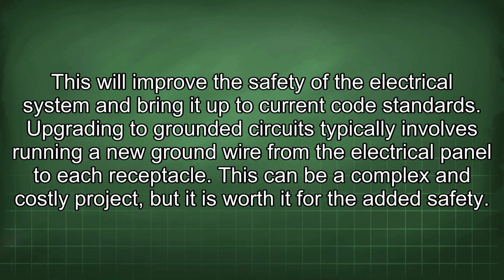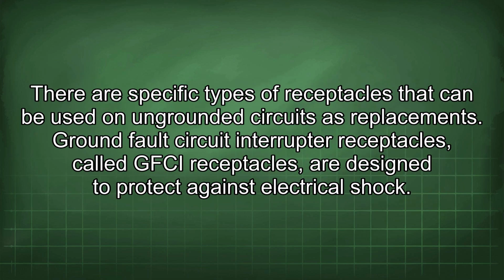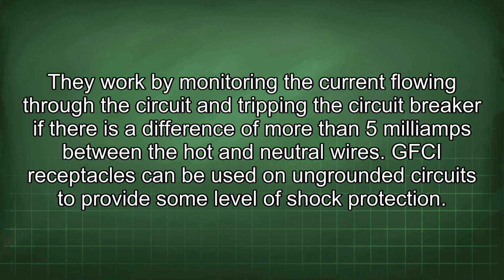Upgrading to grounded circuits typically involves running a new ground wire from the electrical panel to each receptacle. This can be a complex and costly project, but it is worth it for the added safety. There are specific types of receptacles that can be used on ungrounded circuits as replacements. Ground fault circuit interrupter receptacles, called GFCI receptacles, are designed to protect against electrical shock. They work by monitoring the current flowing through the circuit and tripping the circuit breaker if there is a difference of more than 5 mA between the hot and neutral wires. GFCI receptacles can be used on ungrounded circuits to provide some level of shock protection.